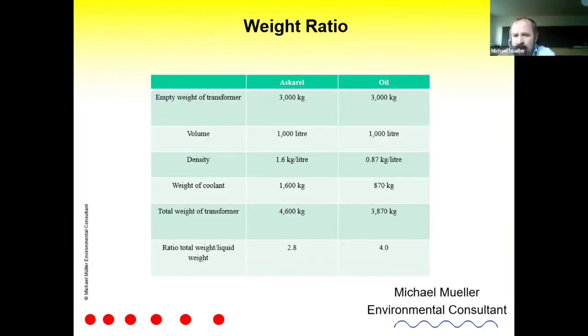In case of the oil transformer, we have 3,870 kilo. Now you divide total weight by liquid weight. The ratio is 2.8 in case of Askarel, and it's 4 in case of oil. That is an absolutely good hint whether you have an Askarel transformer or an oil transformer. It only goes for Askarel transformers, not for oil transformers with PCB cross-contamination. That does not work. Okay, the next slide, please.